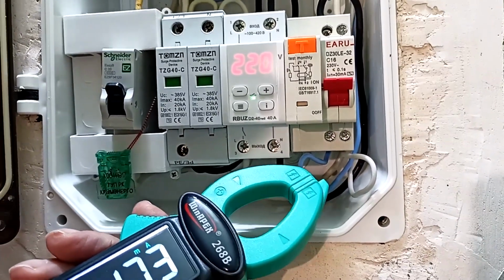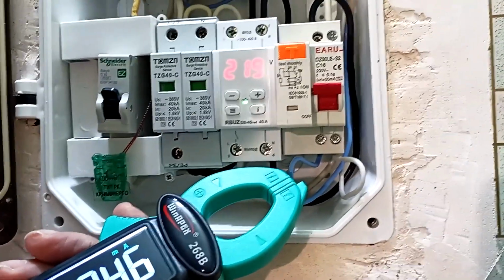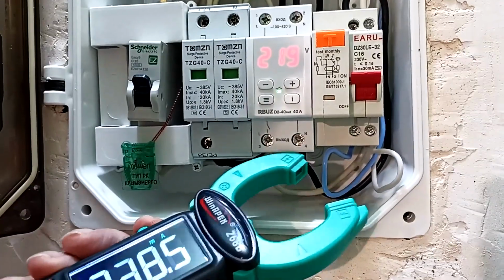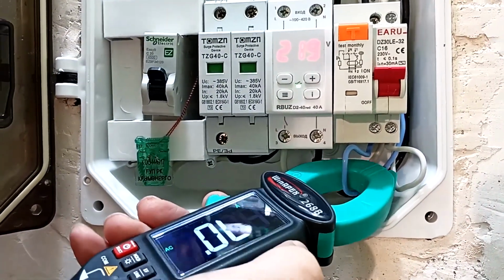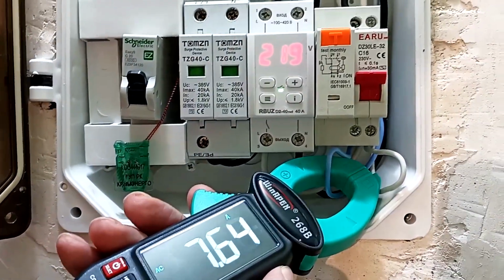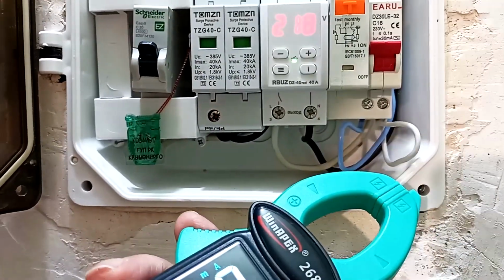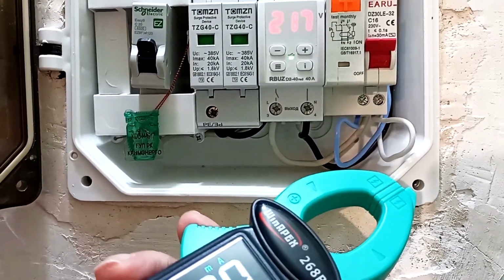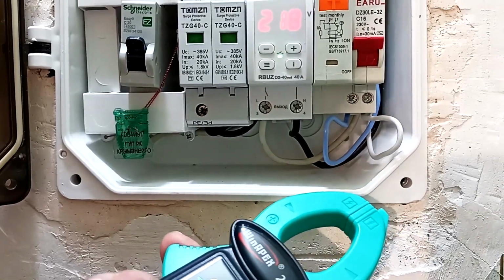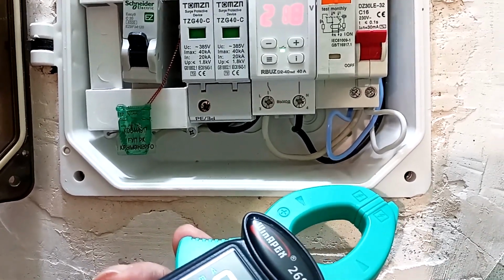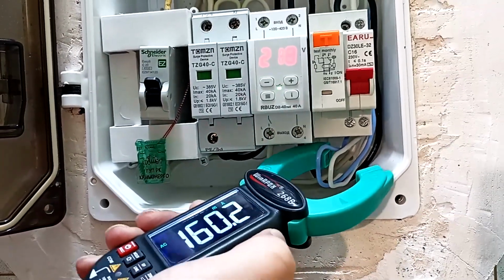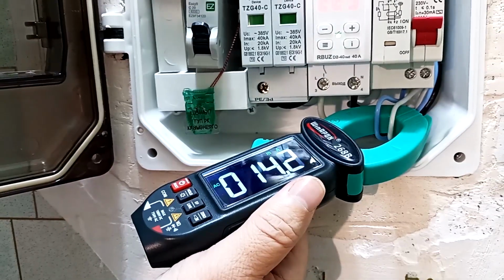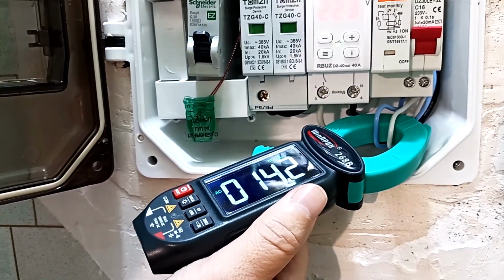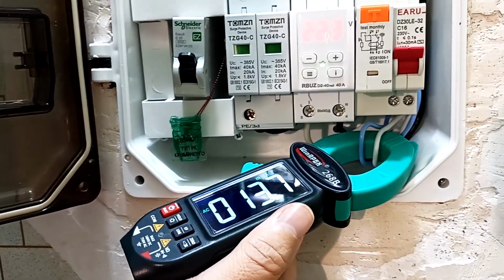In order to measure the circuit current, we need to turn on the device to measure alternating current. We capture a phase or zero, and it shows that 8 amp is consumed. In order for us to measure the leakage, we need to capture both wires, both zero and phase. We captured both phase and zero. We get 14 milliamp leakage.